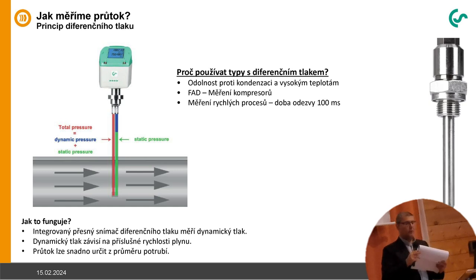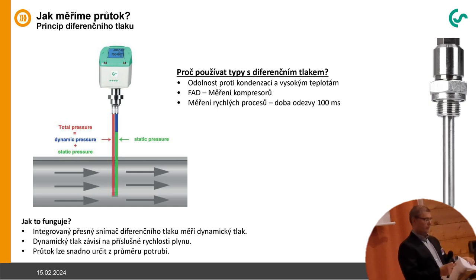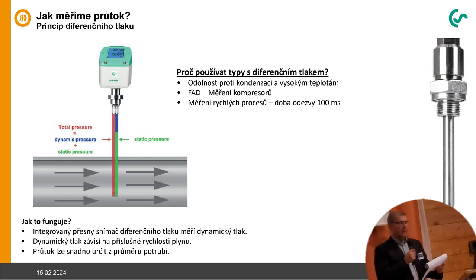In comparison to this, we also have a second type of sensor. The second type of sensor is a differential pressure measuring principle based on the so-called pitot tube principle. And this is very robust against condensation and high temperatures, so it could be used for the so-called free air delivery measurement of the compressor, FAD measurement. And it's a measurement for when you have very fast processes and you need a very quick response time.